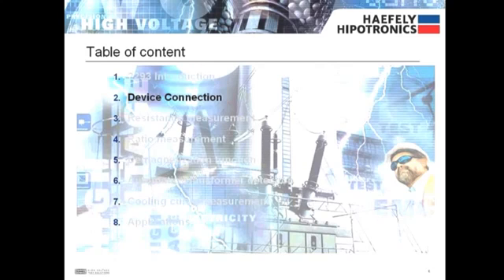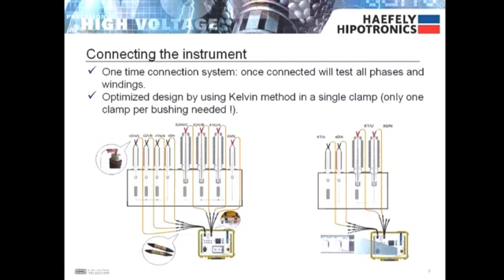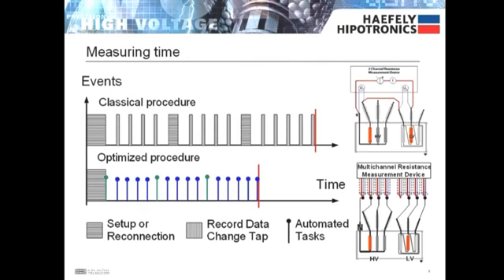Next is the device connection. The 2293 has a one-time connection system which means the user connects one clamp per bushing just once and then can measure all phases and windings. This cuts down on the total test time when compared to the classical procedure of measuring winding resistance which involves several reconnections.